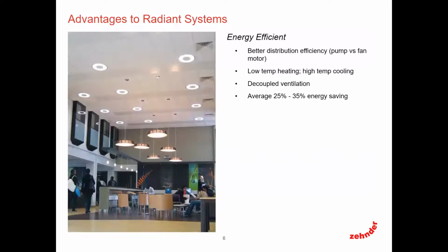Advantages of radiant systems. Why would we want to use a radiant system, whether it's heating or cooling? Well, generally, it's going to be more efficient. And when you look at these as design engineers, I want you to think of this as a tool for your toolbox. Radiant is another tool that you can utilize in your design. When you take that holistic approach towards your building and you're trying to build an energy efficient system for the commercial space, this is just another tool, right? Water holds more energy per unit volume, and it's cheaper to move it from point A to point B than air and fans, right?